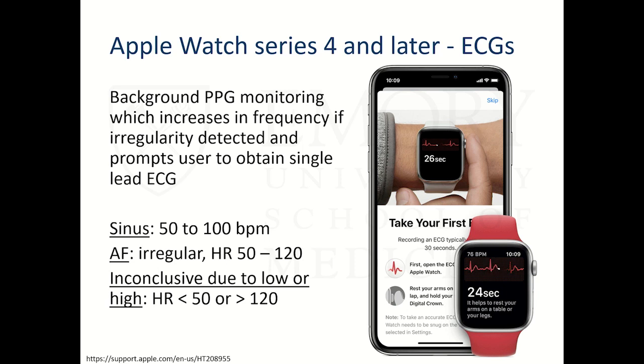The way the single lead ECG works is if you can imagine wearing a watch on your left wrist and you embed an ECG electrode on the back of the watch, right where those LED sensors are, and then you take the finger on the right hand and touch that to the crown of the watch, and you embed another ECG electrode on the crown. Now, in essence, what you've got is a right arm, left arm ECG, and you get something that looks very much like ECG lead 1. And most of the devices that incorporate this kind of ECG screening use a right arm, left arm electrode of some variety and get something that looks like ECG lead 1. So the big fanfare was that Apple had incorporated a way to generate a single lead ECG from the watch.